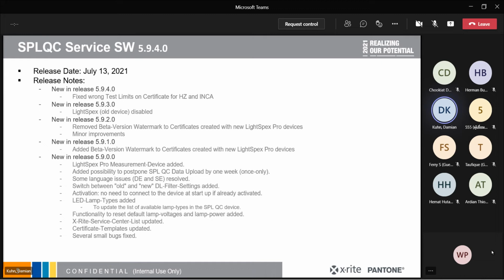So with that new version, you can actually, one, download those additional LED light sources into the device, but then of course you can also change the configuration of the SPLQC so that it includes that LED light source at the fluorescent lamp position where you have physically installed it. It also allows you to recalibrate and recertify an SPLQC device with such a supported LED light source installed. So that's one of the changes we made to the new version, and I'm going to show that when we look at the instrument and the software itself.